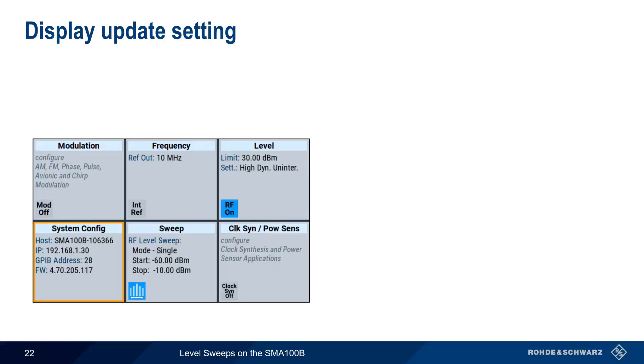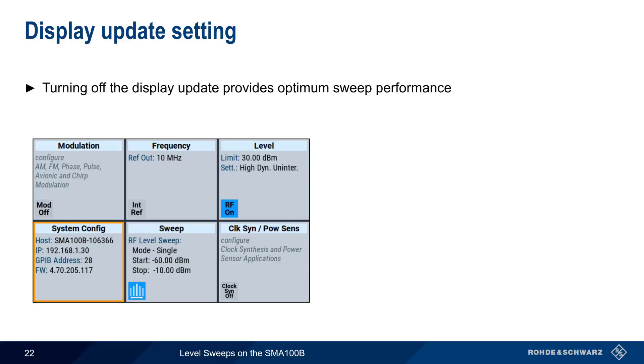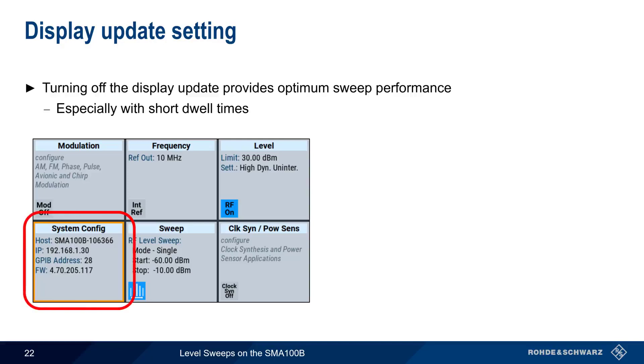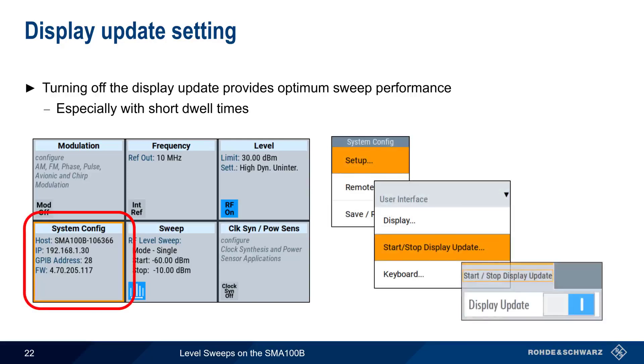One final configuration parameter that might be useful is the Display Update setting. In some cases, disabling display updates can improve sweep performance, especially in the case of sweeps with very short dwell times. To disable updates, press the System Config tile, then choose Setup and Start Stop Display Update. Disabling Display Update simply keeps the level value in the SMA GUI from updating. All other GUI parameters and menus are still visible and active.